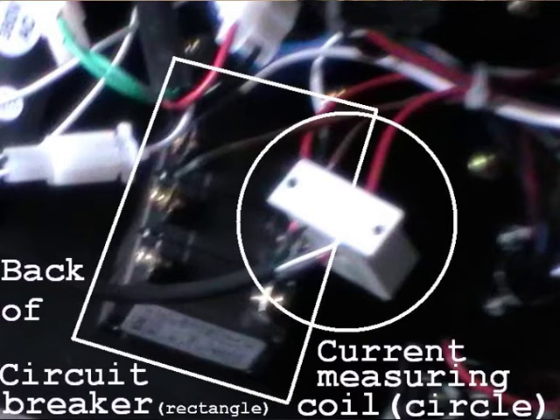And that is that one of the phases is not connected to the milling machine, or at least to that motor. The main spindle works on the milling machine, so that motor is getting all three phases, but the one for the rapid traverse is not. I'm pretty sure there's actually no electrical wiring problem, and I'm just guessing that it is most likely to be one of the contactors, or the contact on the contactor or switch that turns that motor on, that's just not making contact. It's corroded, rusted, whatever you want to call it.